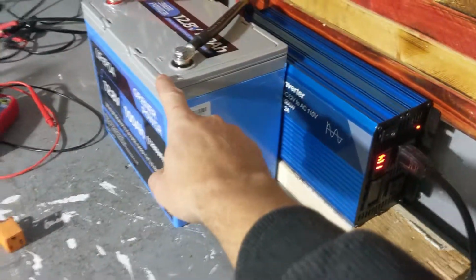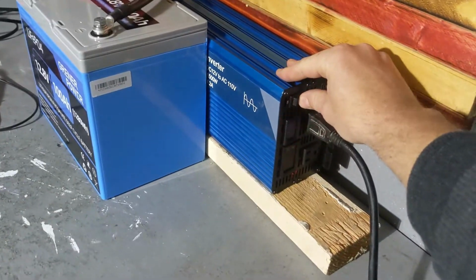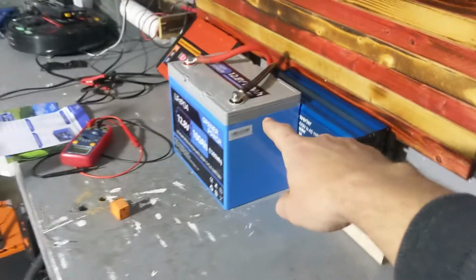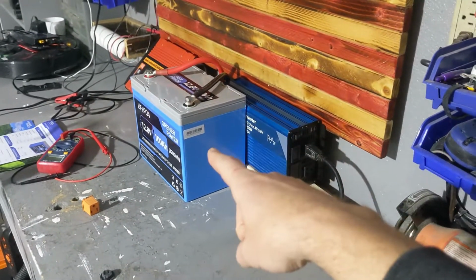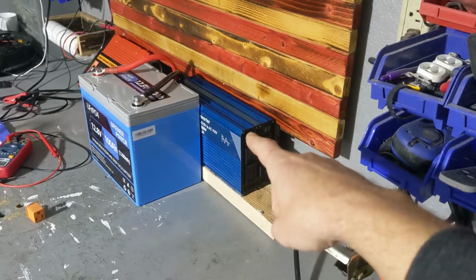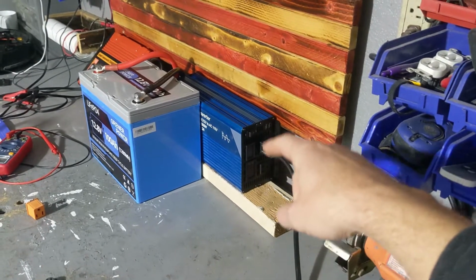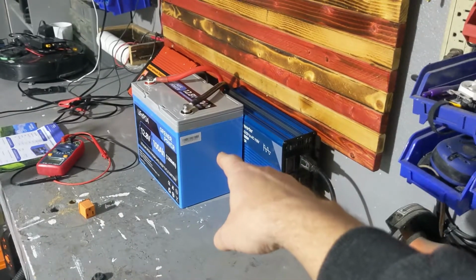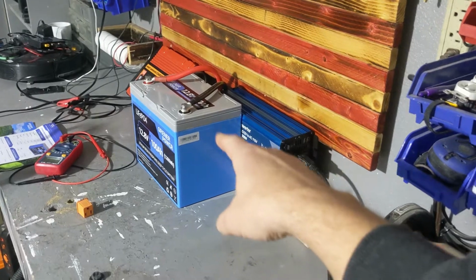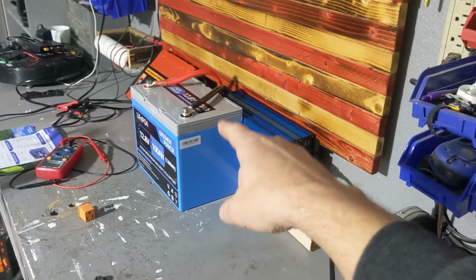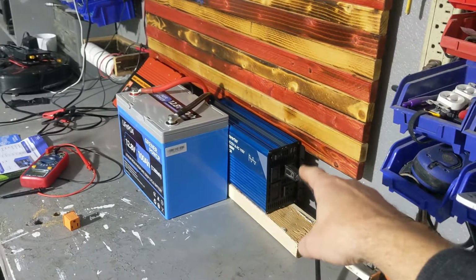So this BMS, I'm going to stop this because it's making too much noise. But this BMS did not turn off. The inverter has a protection system that kicked in before the BMS cut off. So that one cuts off under 10 volts, this one cut off around 10.4 or so.